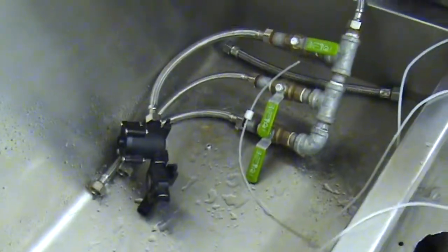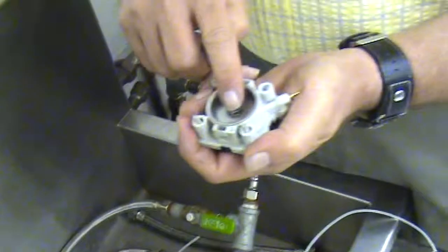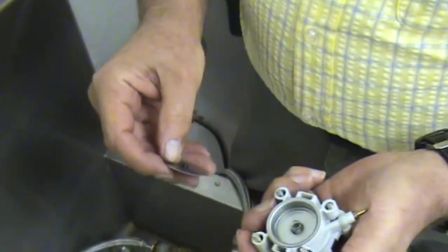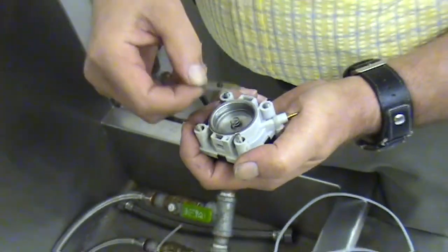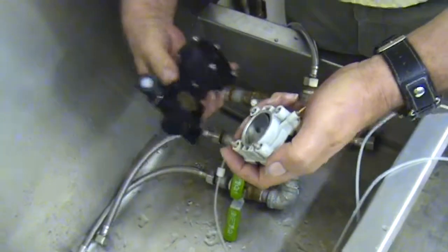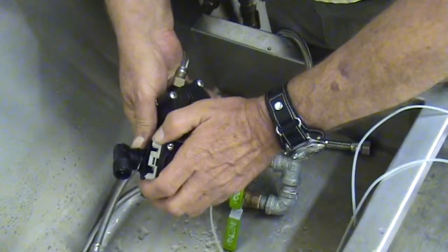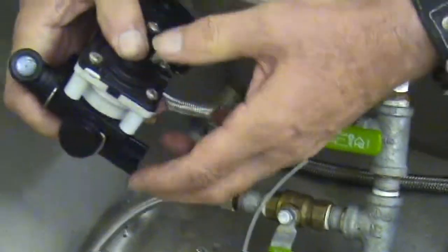Your spring, of course, you want to be sure it's in the upright position in the recess provided for it. The small side of the rubber and the metal disc should face the spring. A large face should face the water diaphragm in the valve.